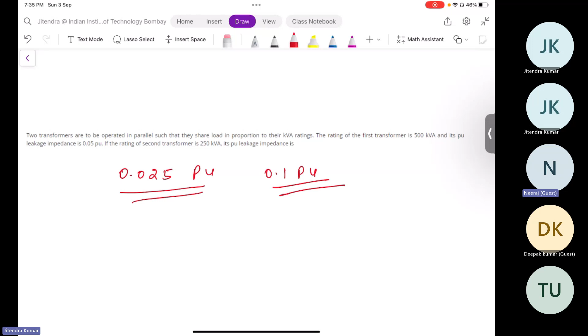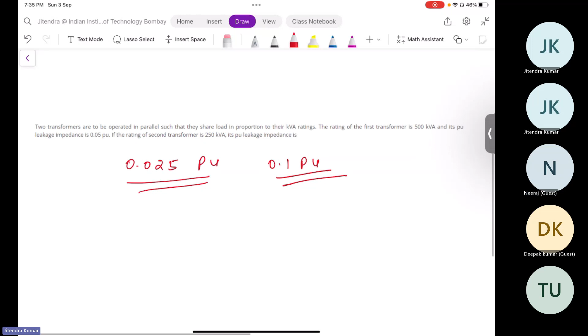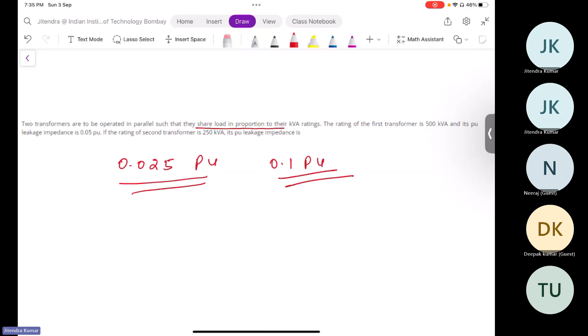See, I told you, when load is shared in proportion to their kVA ratings, it is written here very clearly: share load in proportion to their kVA ratings. In that case Z1 per unit becomes equal to Z2 per unit. One condition I also mentioned there: on own base.